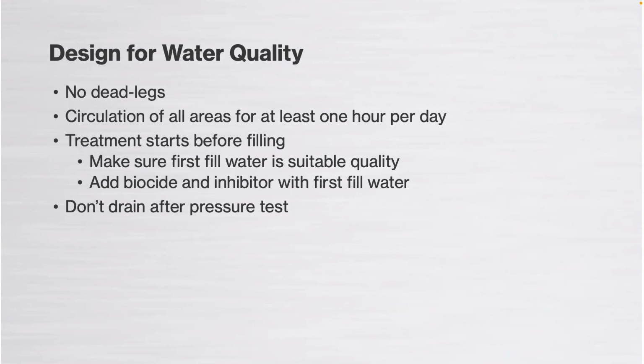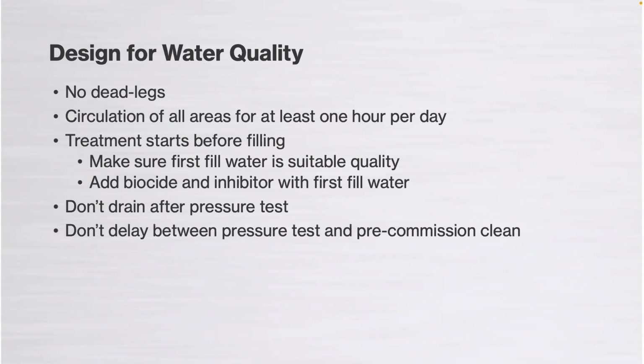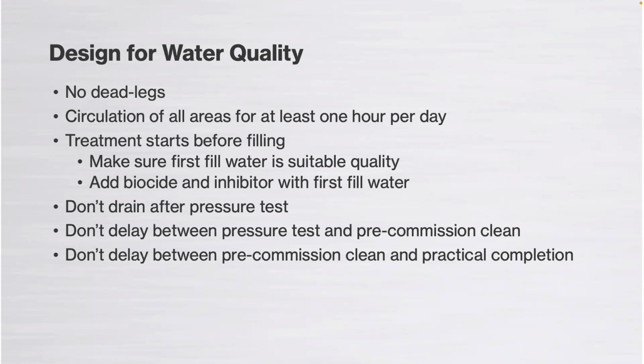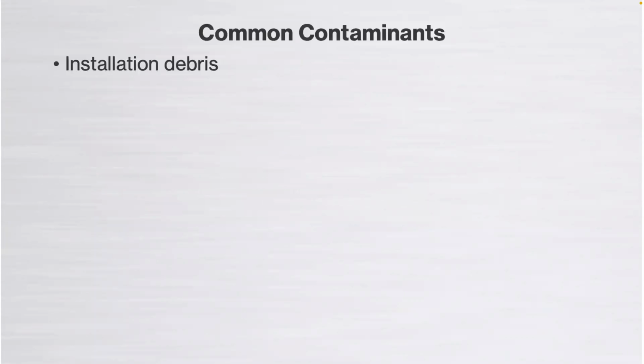I came across a client that was actually draining a chilled system in the winter, and they were saying, but we always get problems once we've refilled the system. Come the summer, we've always got water quality issues. And I found that, I know I'm sort of from a water treatment background, but I thought that was rather bizarre that they wondered why. Don't delay between pressure test and pre-commission cleaning, and then no delay between pre-commission cleaning and practical completion. So essentially design the whole program accordingly, right from start to finish, making sure that's designed all the way through.